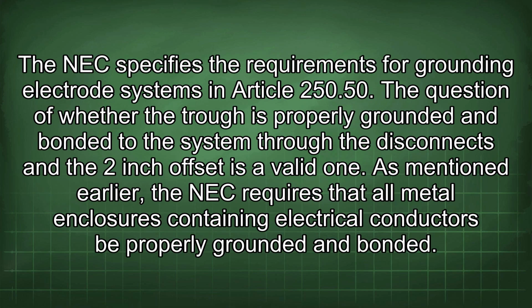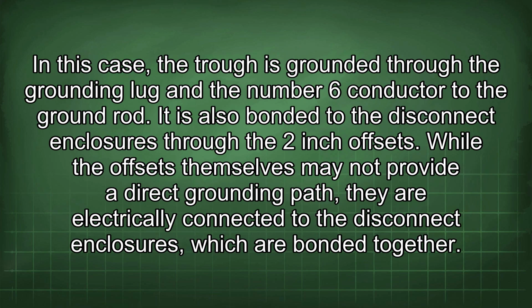The NEC specifies the requirements for grounding electrode systems in Article 250.50. The question of whether the trough is properly grounded and bonded to the system through the disconnects and the 2-inch offset is a valid one. As mentioned earlier, the NEC requires that all metal enclosures containing electrical conductors be properly grounded and bonded. In this case, the trough is grounded through the grounding lug and the number 6 conductor to the ground rod. It is also bonded to the disconnect enclosures through the 2-inch offsets.